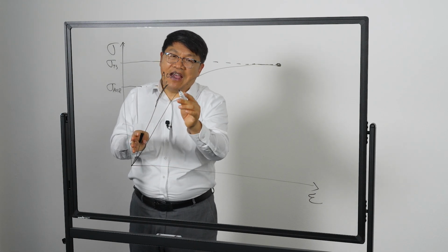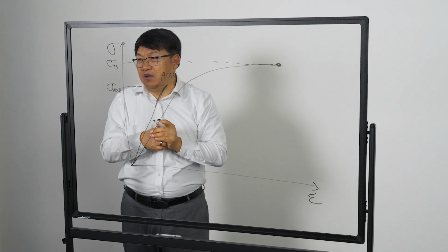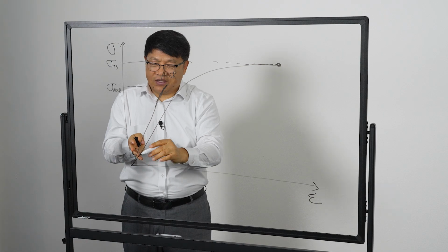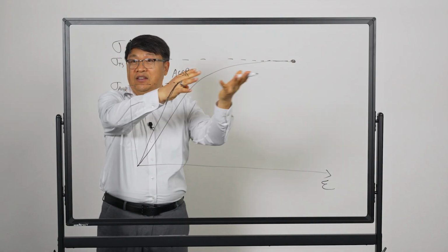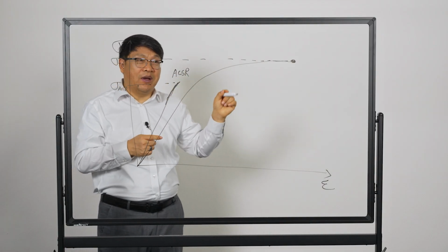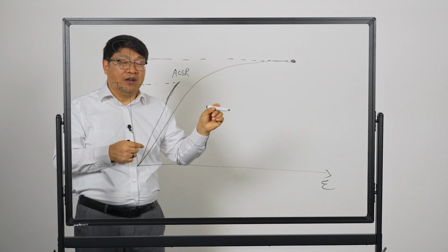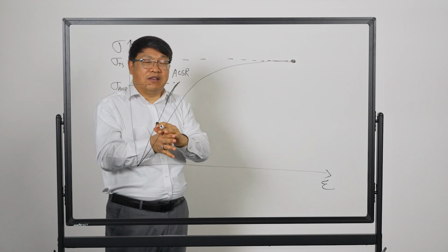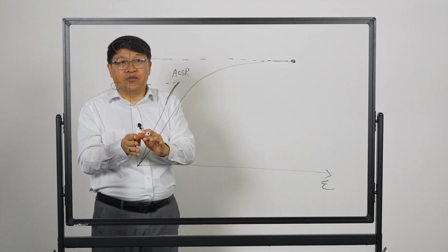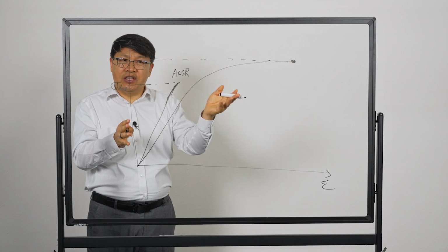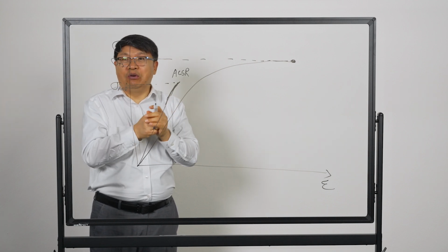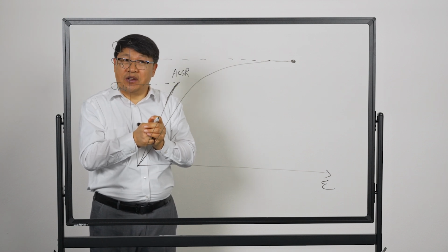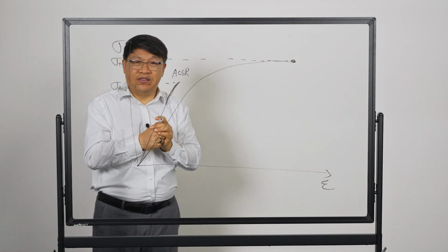you do not have that linear stress strain curve. So we have to use what is called polynomials to approximate how the stress and strain is behaving. And this is fundamentally important for sag-tension analysis in conductors, especially the newer conductors. Countries that are still using a linear model need to consider a polynomial relationship for stress strain in sag-tension analysis.